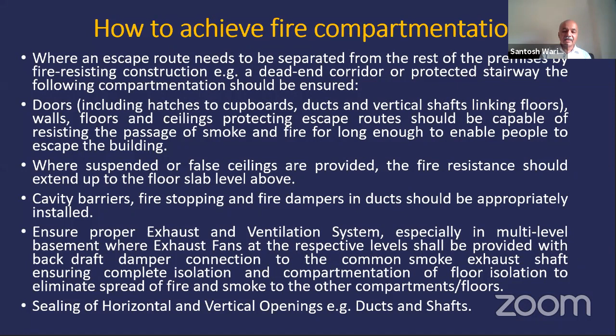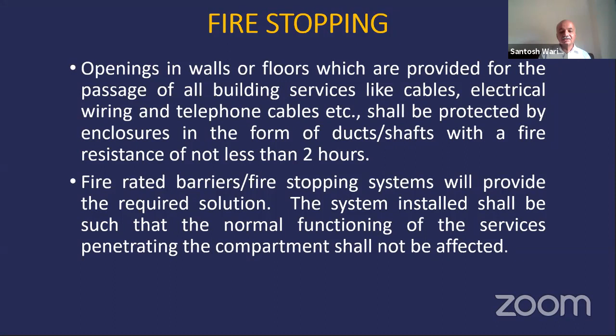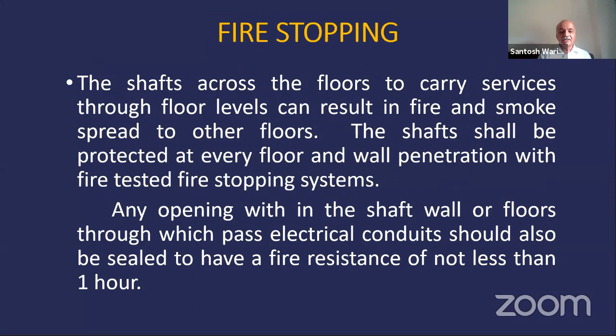The fire stoppings which are used for sealing of these ducts, cables, electrical wiring, telephone cables, fiber optic, or whatever services passing through horizontally or vertically, should have a minimum of 2 hours fire resistance, and they should have the proper functioning and testing certificate to that effect. So that is very much important as far as fire compartmentalization is concerned.